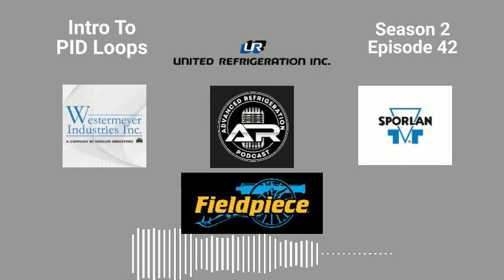Because if you're trying to tune, like Kevin so eloquently put it, if you're trying to tune shit, you're going to get shit. So if the thing that you're trying to tune isn't set up from the get-go, you're fighting an uphill battle. Actually, remember the guy posted, it was a flash tank. He had a flash tank problem, right? And he was asking about PID loop. I don't know if I was texting him via Facebook or something, but I said, hey, why don't you try to check your steps first? And that's essentially what he found. The steps for that valve was set for, I think, 6386, and it should have been 2500. So something as simple as that might take care of all your problems.